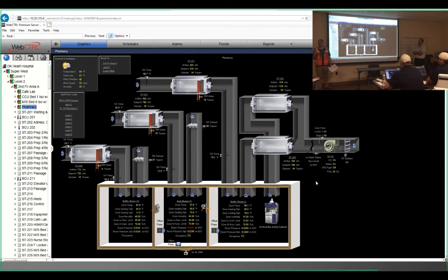The challenge is that on the back side of that, it's all air handler unit return. It's not an exhaust fan like in the negative buffer room. So we don't have control over the static on that, because as the whole floor gets satisfied, the fan ramps down and the return static comes down, and those dampers become less control-y. That's the technical term. So it was a big challenge.